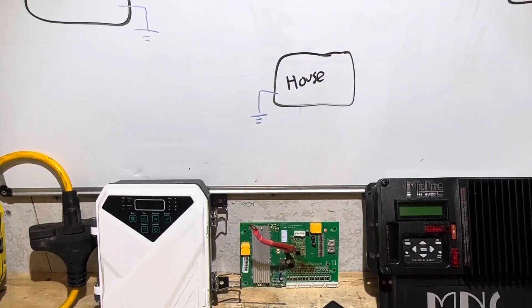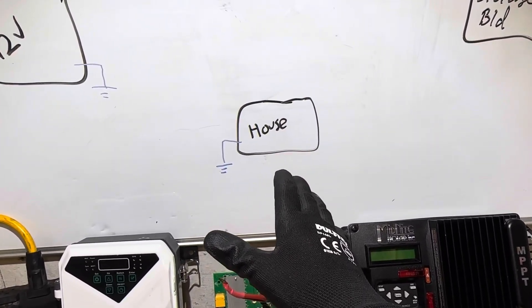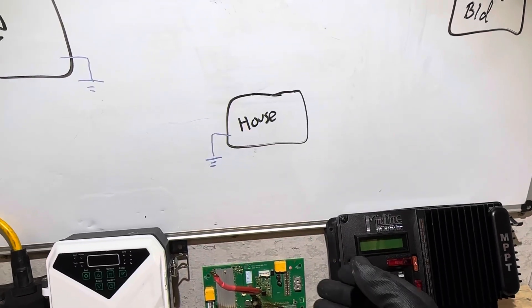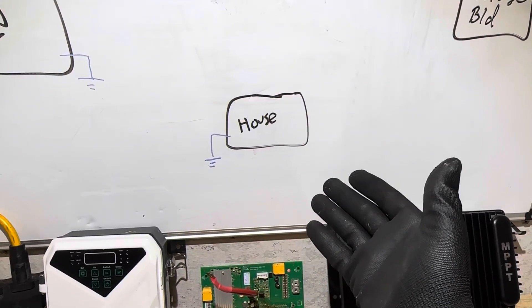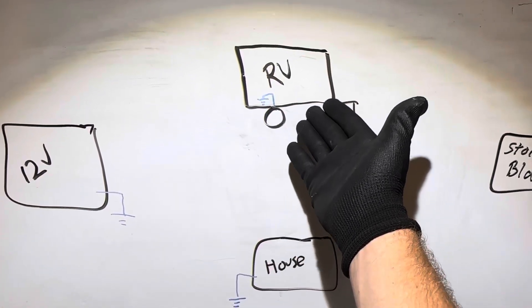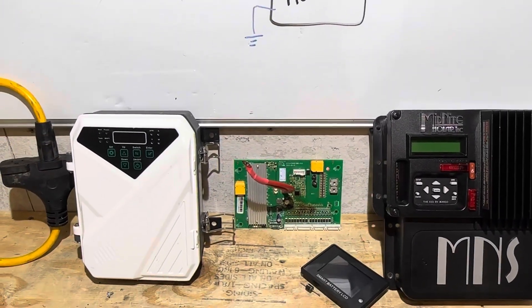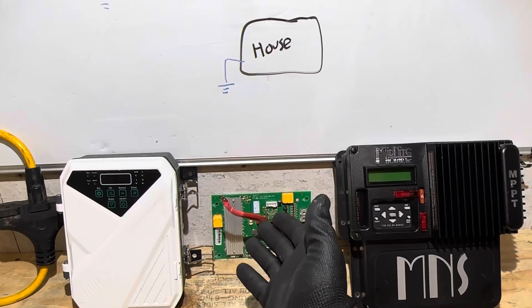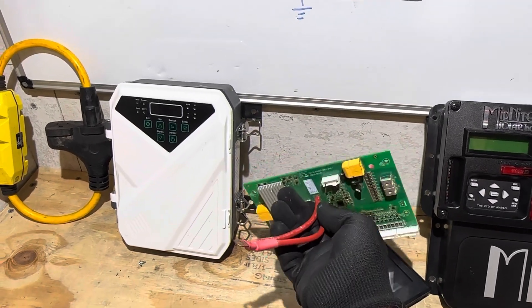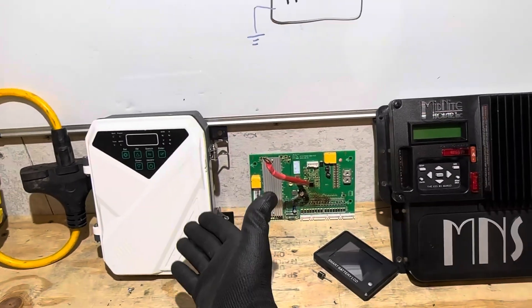So what are the next steps? I thought I'd put all the protection I needed on the house system, but now I'm looking at some TVS — transient voltage suppression devices — for batteries, for each individual server rack battery to have its own TVS. I've talked to a couple of electronics guys and am trying to pick out some parts to maybe harden it up a little bit more. But then again, a non-hardened system rode through just fine, so maybe just have redundancy. And batteries just sitting there can get cooked, which means I'd have to put TVS or MOVs on just batteries sitting static. It could also be just due to the robustness of the hardware and the boards.